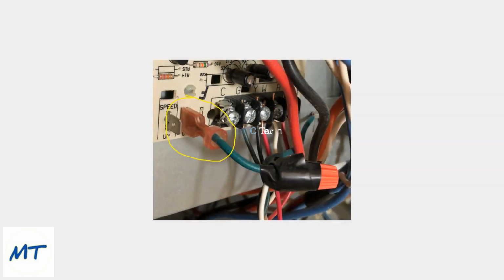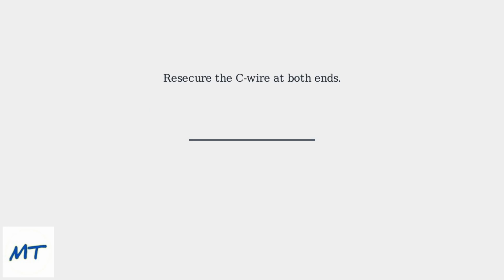A common DIY success story involves a loose C-wire connection. Many homeowners fix their Pro1 T705 thermostat by checking the C-wire at both the thermostat and HVAC unit. If your thermostat fails, first check the C-wire connection at the thermostat terminals, then inspect the HVAC unit's control board where the wire terminates. To fix it, resecure the C-wire connection by tightening the terminal screws at both the thermostat and the HVAC control board.